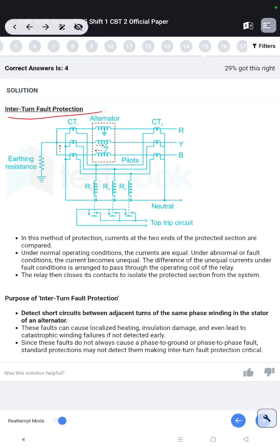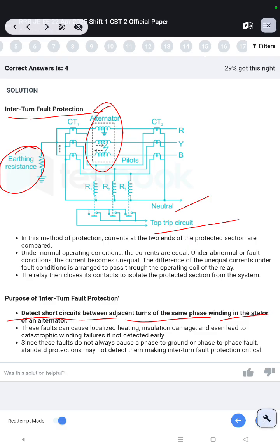Interturn fault protection. Alternator: earthing resistance, neutral, top trip circuit. The purpose of interturn fault protection is to detect a short circuit between adjacent turns of the same phase winding in the stator of an alternator.